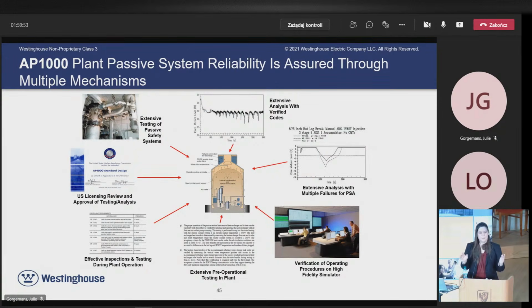That's what we do at the design stage. Once we're building an AP1000 unit, we also need to verify that the specific safety systems built in that unit meet the assumptions made in those analyses. So we have an extensive startup program to verify the performance of the safety systems as built—and yes, it can be tested.